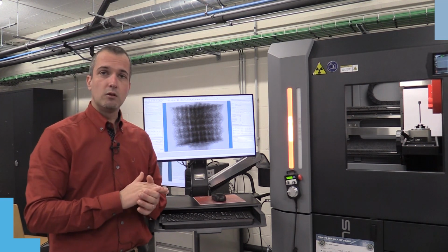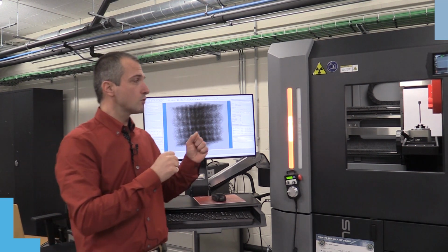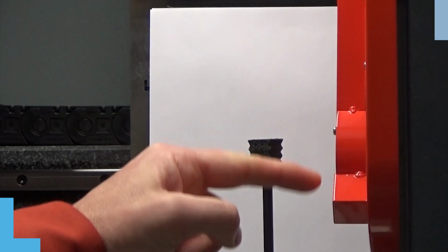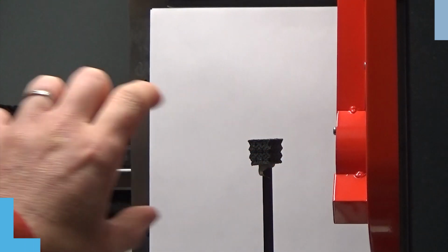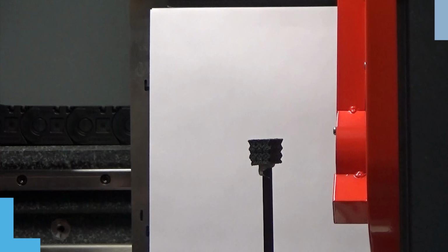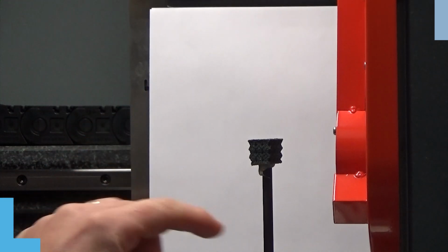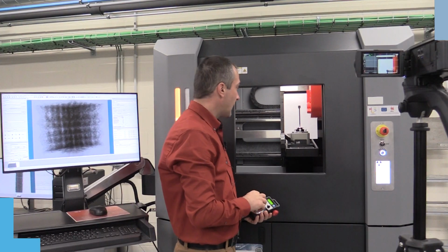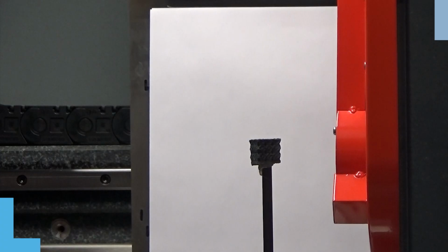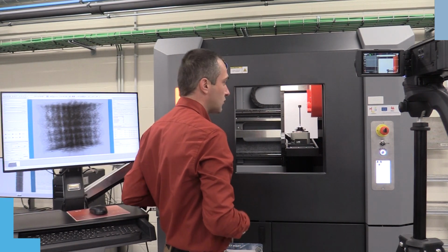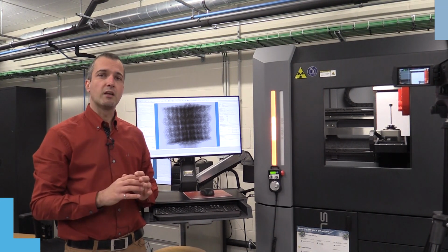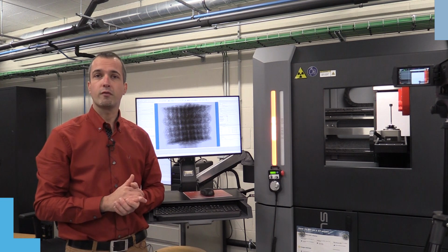The way the tomographs work is we have a source of X-ray, which is on the right side here, and those X-rays are emitted and go through the sample and then reach a sensor which is on the left. For the acquisition, we're going to rotate the sample 360 degrees and typically take a picture every now and then. Depending on the resolution that we want to achieve and the signal to noise, we will record many images, up to a few thousand.